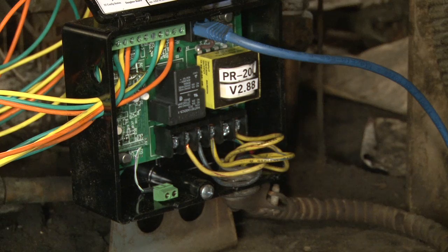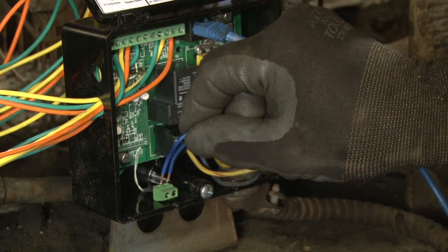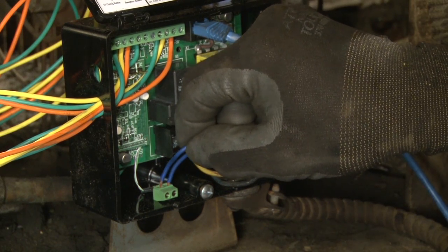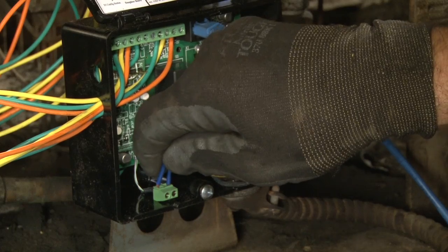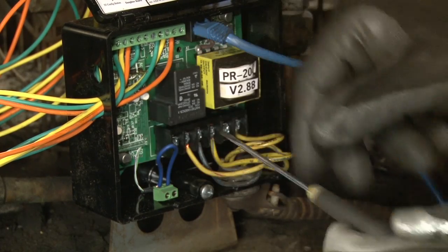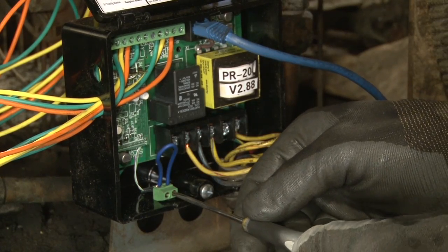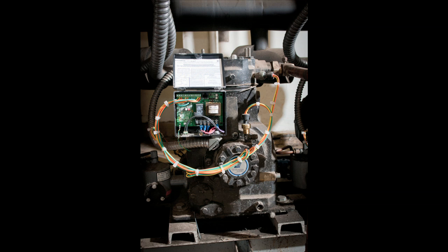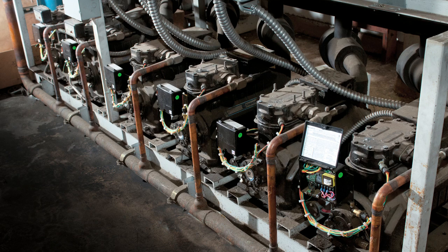This PressuRITE contains a pair of digital input contacts that need to be jumpered because it's not connected to a network. Once this is done, the PressuRITE is ready to go. This PressuRITE retrofit installation is now complete. Shown here is a full PressuRITE compressor rack installation.